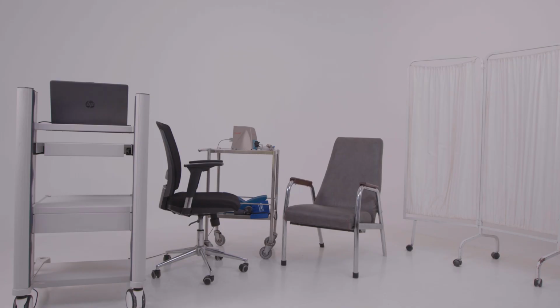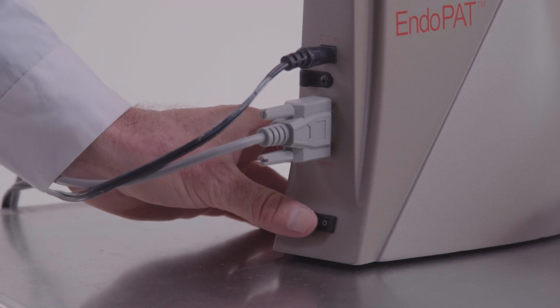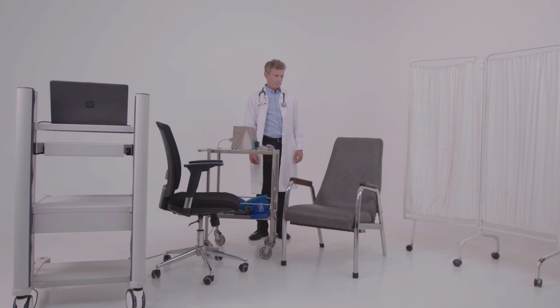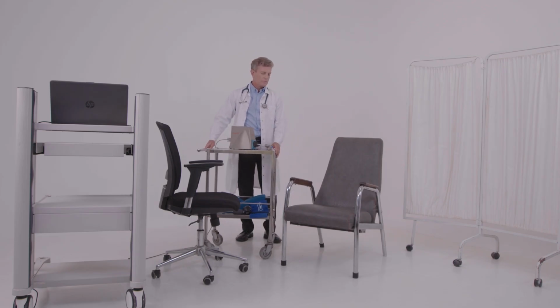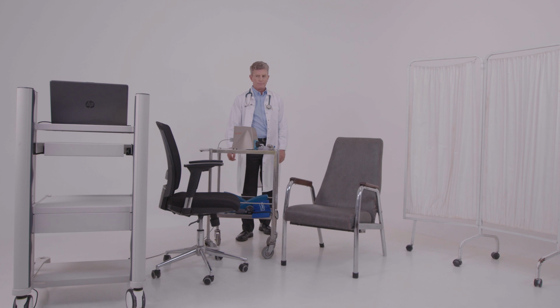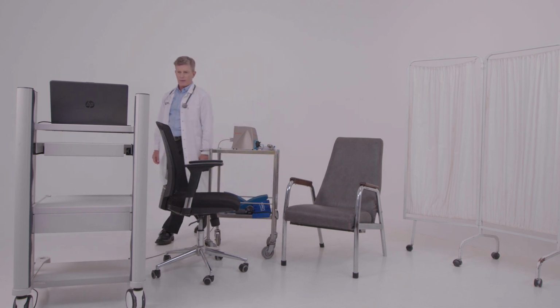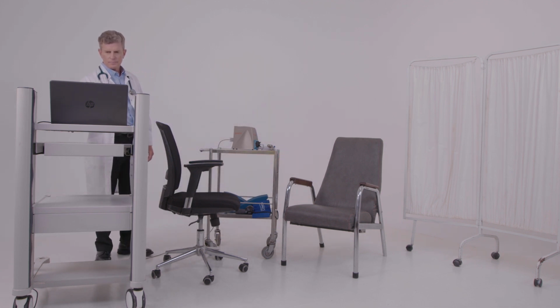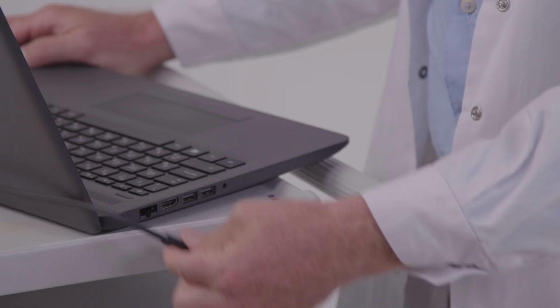This video will show you how to prepare a study with the EndoPAT2000. First, turn on the system for at least 20 minutes before starting the study. Make sure the device is about 1 to 2 feet or 33 to 66 centimeters from the patient, and the laptop screen is positioned away from the patient. It is recommended for the laptop and the device to be on a trolley.